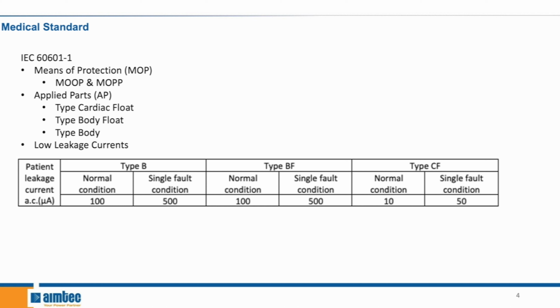Next, we'll be moving on to applied parts. Depending on the type of medical device, physical connections between the patients and the medical devices may be required. Such connections can carry leakage current and can cause potential danger to the patients. To determine the required level of protection, the applied parts, which are parts that will have contact with the patient under normal use, are categorized into 3 different types. And the 3 different types are cardiac float, body float, and body.